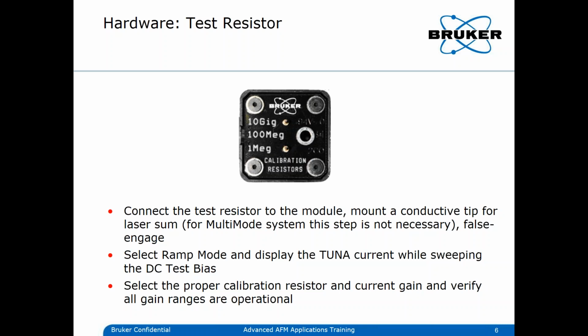And for testing, you should connect the test resistor to the module. You would have to mount a conductive tip to get a laser sum for the Icon system. That's not necessary for the MultiMode. Then you would false engage and select the ramp mode and display the TUNA current while sweeping a test bias. But I'm coming to that later again on an extra table concerning the troubleshooting. And then you would basically look for your IV curve there.